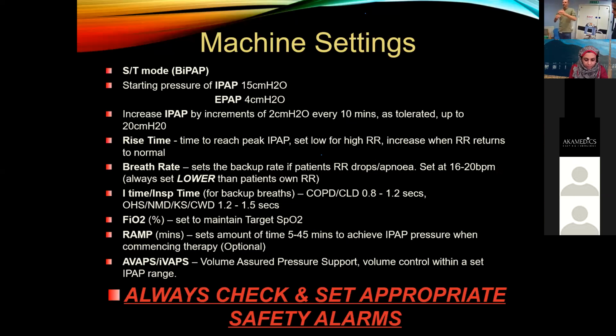We would then set an IPAP range, so a pressure range, and we would say a minimum IPAP of 5, 6, 7, 8, whatever you choose it to be, and a maximum IPAP pressure of 20, 25, 30, whatever you want it to be. The machine will then automatically use whatever IPAP pressure it needs to deliver to guarantee your patient has an expired tidal volume of 500 mils. So traditionally we would just tell the machine what IPAP we want it to use. With AVAPS or iVAPS, we tell the machine what we want our patient's tidal volume to be, and the machine decides on the pressure it needs to use depending on the range that we give it.